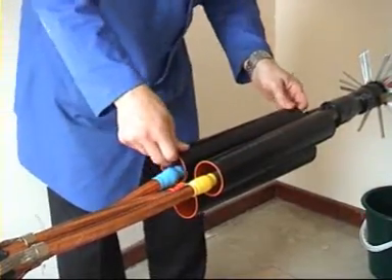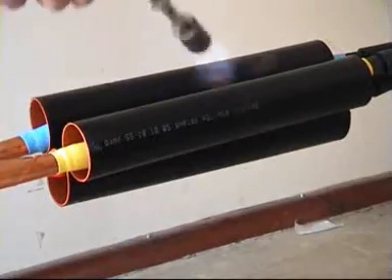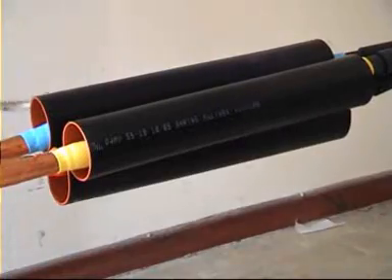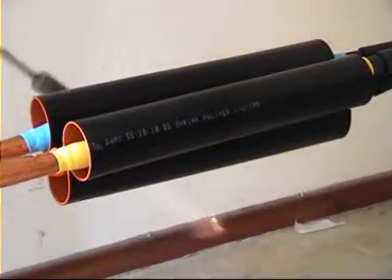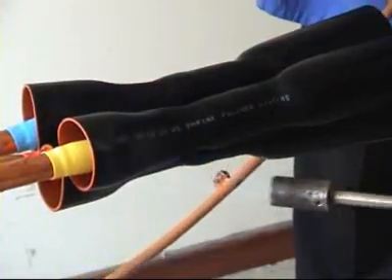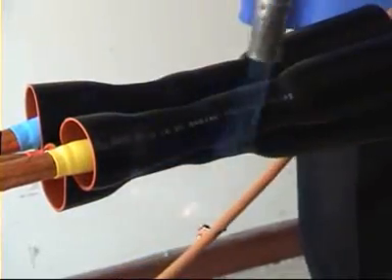Position the connector insulation tube centrally and with your heat source shrink from the centre to one end at a time. Keep the flame moving all around the tubes to ensure an even wall thickness.